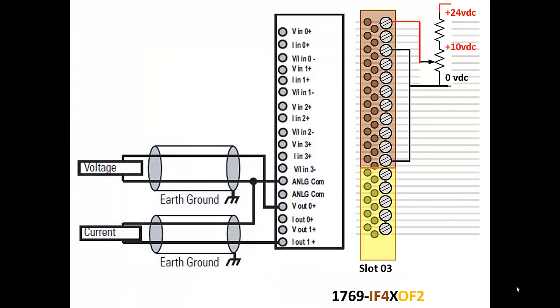This is the wiring diagram for this particular module for the outputs, the other half, the bottom half. For analog voltage outputs, we will use the absolute most inexpensive option in case you decide to build one of these: a zero to ten volt DC meter, or what your friends call a gauge. The module is supplying the output voltage to the meter by controlling the 24 volt DC applied at the top of the module. The module is designed to work with 24 volts DC. It depends on the kind of module whether it's an external power or internal. With this particular module, we can use external power or internal power. There's a switch in the card that allows you to pick voltage out the backplane or external voltage.